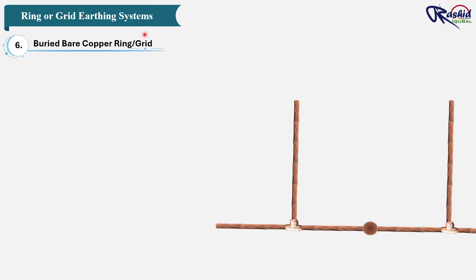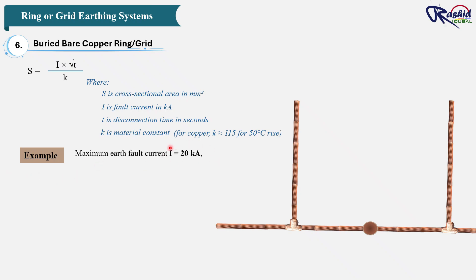Now we will learn the conductor sizing. This buried ring must carry full fault current for the clearing time of the protective device. So we can use this formula: S = I × √T / K, where S is the cross-sectional area in mm², I is the fault current in kilo-amperes, T is the disconnection time in seconds, and K is the material constant. For bare copper conductor, we use K = 115 for 50 degree centigrade. So let's take an example: our maximum earth fault current I = 20 kA, and protection clearing time T = 1 second. So let me substitute this value in the formula: S = 20 × √(1 / 115) = 174 mm². S = 174 mm².